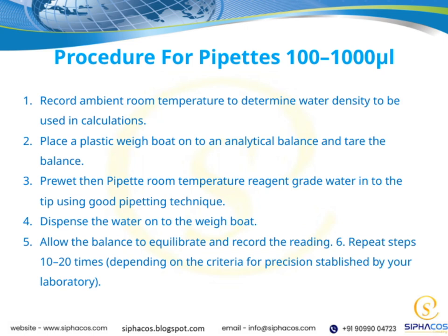Before pipetting, remember to pre-wet the pipette tip with room temperature reagent-grade water. This step minimizes errors caused by the water sticking to the tip and ensures more precise volume delivery. Then, pipette the water into the tip carefully, using good pipetting technique, smooth, consistent, and controlled movements.